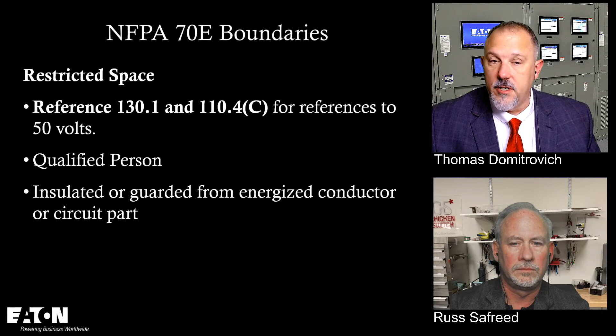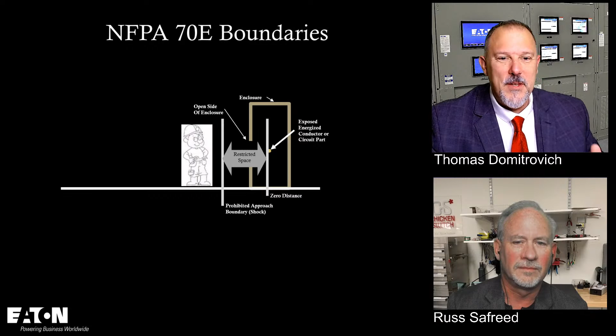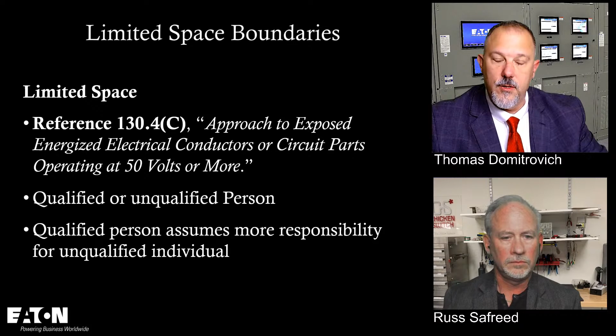We're going to talk about what an arc flash boundary means in a second. So there's your restricted space. I'm not like Ryan and the IAEI or Mike Holt and those guys who have very intensive capabilities in graphics. So that's your limited space boundaries. There's your reference, 130.4C, which talks about exposed electrical conductors and circuit parts. It talks about the difference between a qualified and unqualified person, who has the responsibilities, and what their responsibilities are. Then you get into the limited space, so that boundary is a little bit further. Now you can bring somebody into this space who you have to keep an eye on.